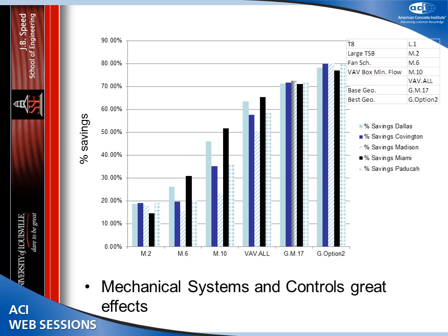We get a similar result, though, when we're looking at the mechanical behavior of the building systems. So controls have a greater effect on the performance. Controls, HVAC systems, how we run that building has the greatest effect on how much energy is used within that building. And what was true in Kentucky is generally true throughout the range of climates in the U.S.